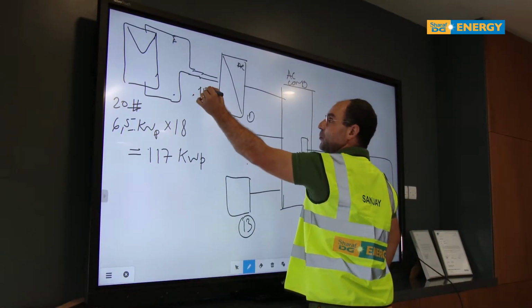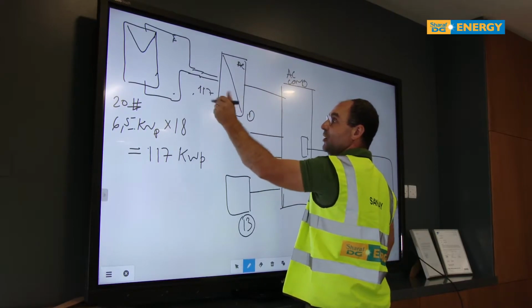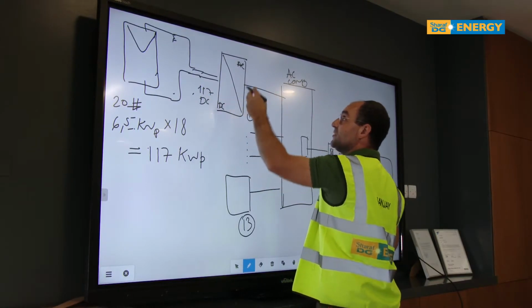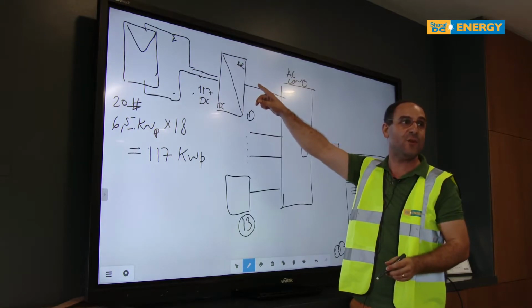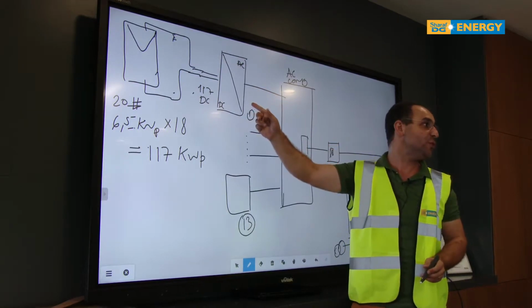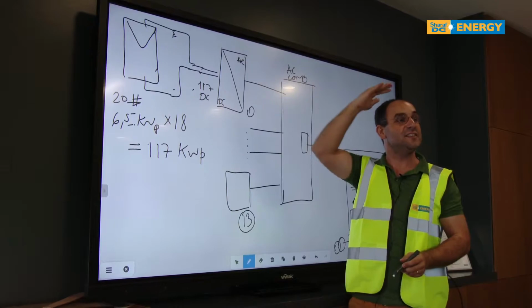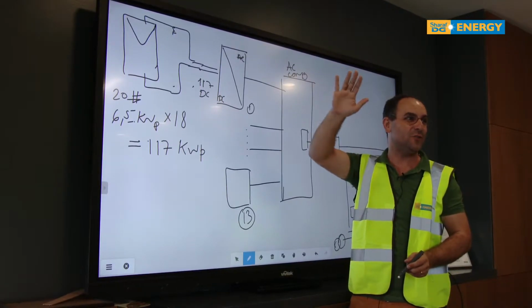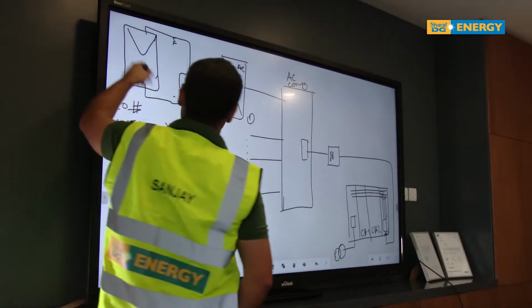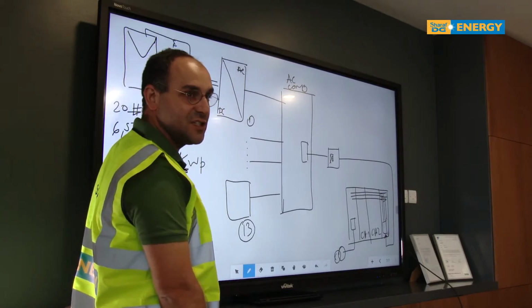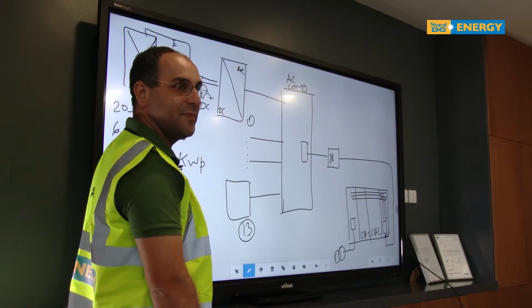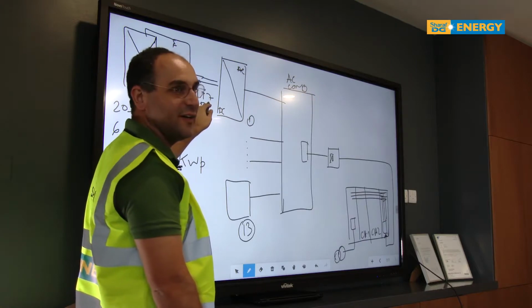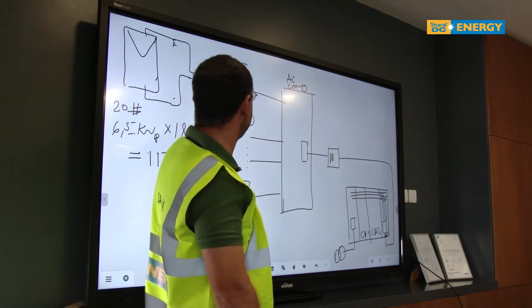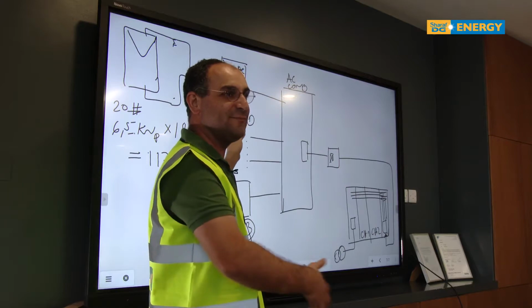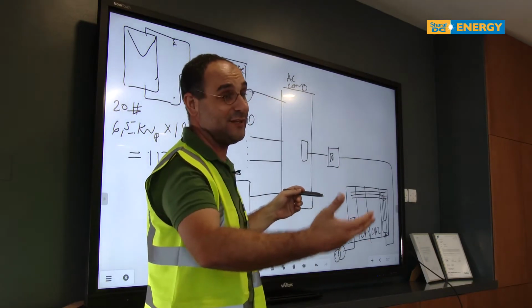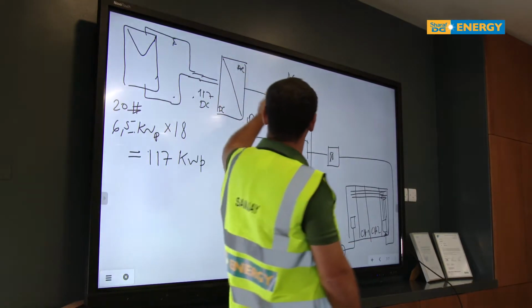We are putting 117 kilowatts DC into an inverter, but we know it only gives you 100. Why do we usually do this? Because there are energy losses throughout the way - dust in the panels, voltage ohmic losses. So we account for a buffer on the DC side to make sure that when you buy the inverter, you're buying something you're going to use. That gives you the 100 kilowatts.